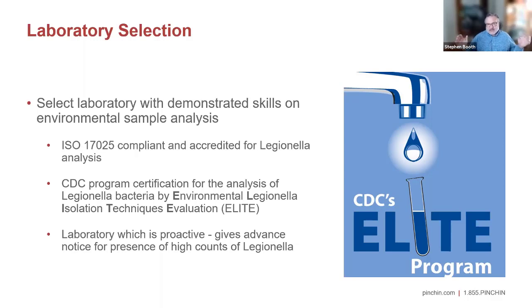The Legionella culturing process takes 10 days. Labs usually do an inspection with a rough count 5 days in—if there's already a problem at that point, there will be a problem at 10 days. Some labs give you a heads up, saying, for example, that of 20 samples, three quarters are already showing high counts at 5 days, which lets you take action earlier rather than later.